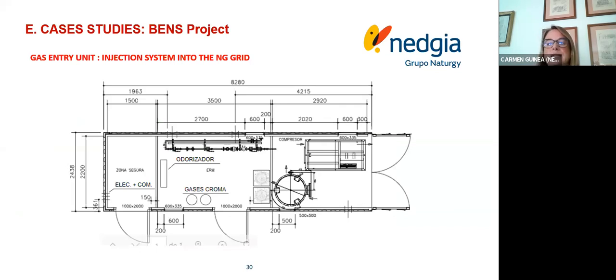This is the drawing of the gas entry unit with the equipment located inside the container. There are 3 rooms: 1 safety room for the electrical and control systems, 1 for the regulating system, and 1 for the compressor. The project requires a booster compressor because the natural gas grid in this area has a pressure of 16 bar, and the biomethane pressure at the outlet of the upgrading is 15 bar. Therefore, it requires a booster compressor to increase it to over 16.